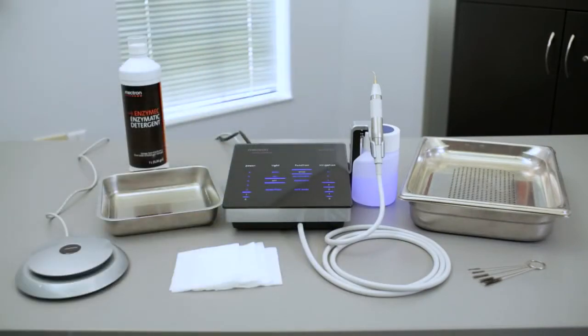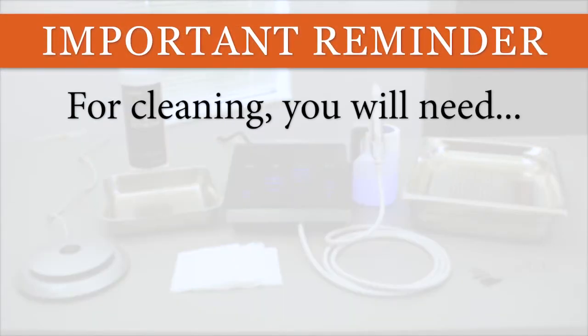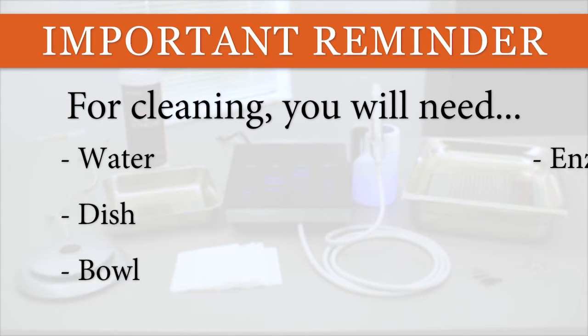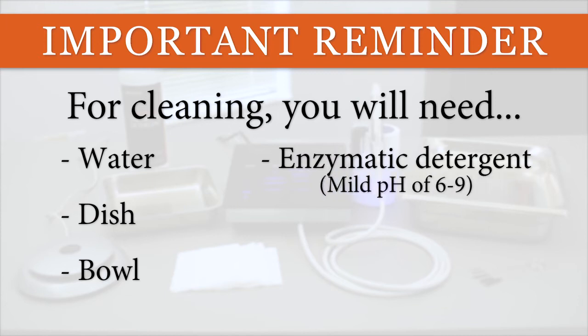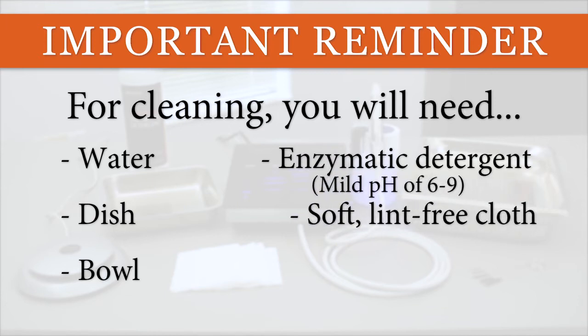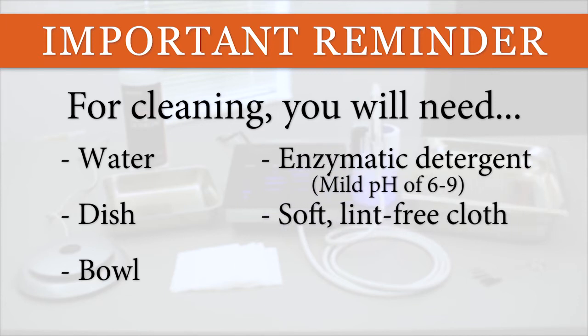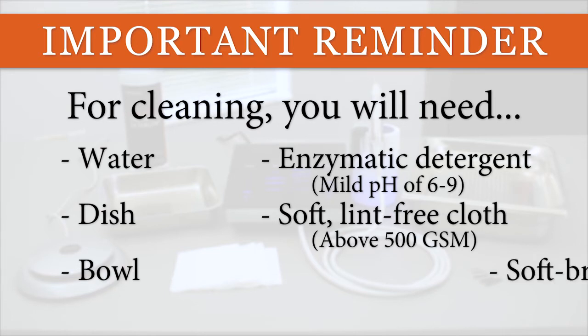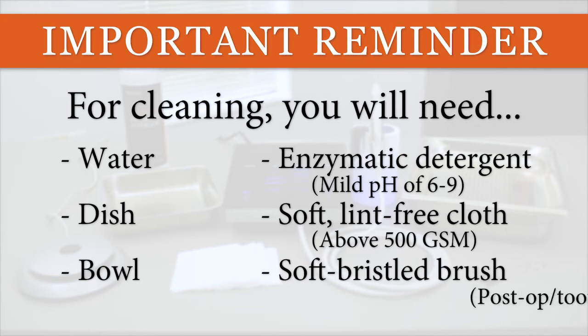Next, we will go over the recommended steps for cleaning and sterilization. To clean and prepare the device and accessories, you will need distilled or sterile water, a dish, a bowl, enzymatic detergent with a mild pH of 6 to 9, a soft, lint-free cloth, such as microfiber, which should be above 500 grams per square meter so that it's less likely to scratch. When laundering, avoid fabric softener to prevent smudging. And a soft-bristled nylon brush, such as a post-op or soft-bristled toothbrush.